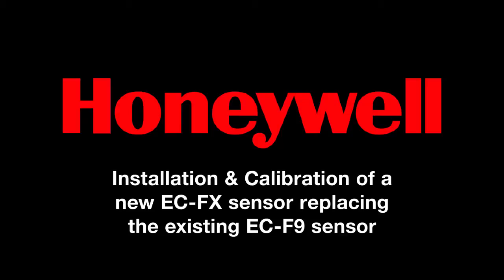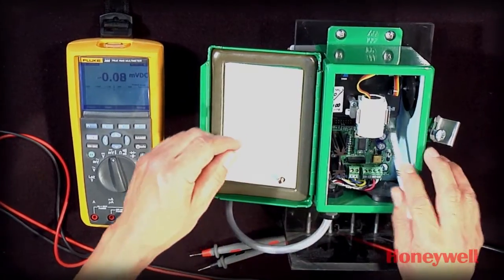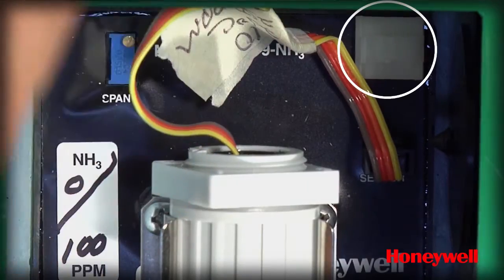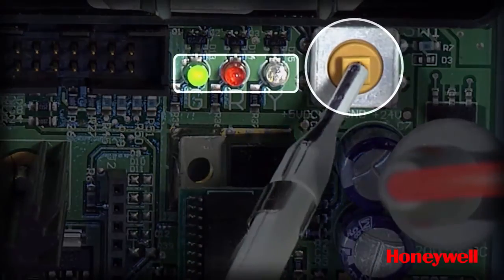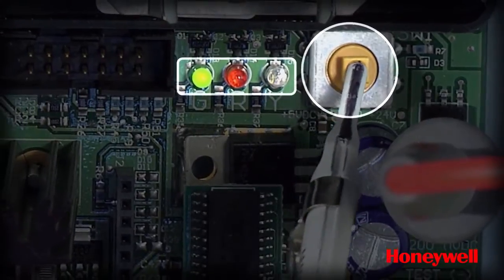This is the procedure to replace and calibrate a EC-F9 sensor with the new EC-FX sensor. First, remove the existing sensor by sliding the ribbon cable from under the retainer clip and then pull the connector from the motherboard. Next, place the unit in factory calibration mode.